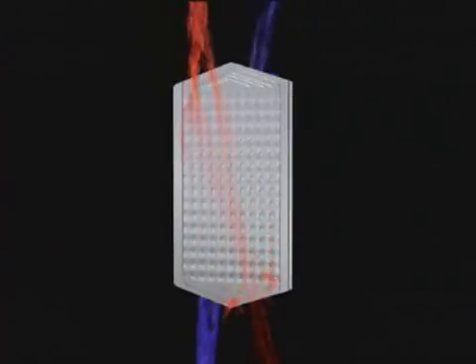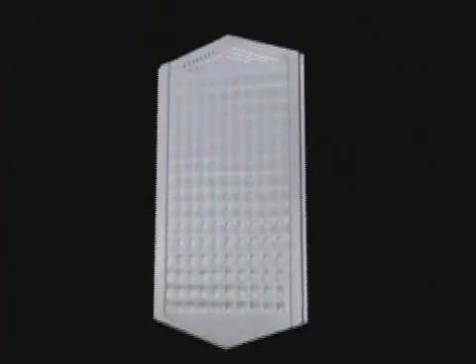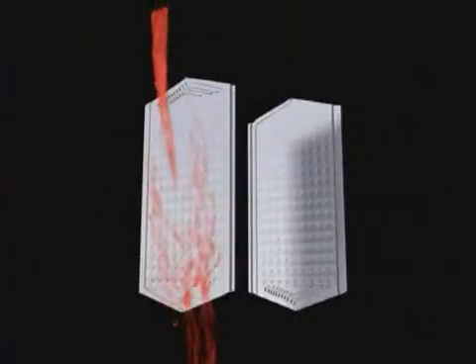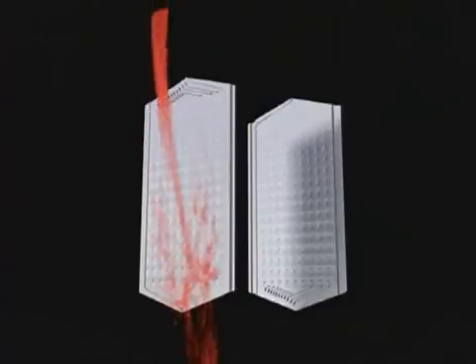This arrangement is the most efficient form of heat transfer and eliminates the typical diagonal temperature profiles found in cross-flow exchangers. The undulations on the plate surfaces provide turbulence and increase the thermal efficiency of the surfaces. Because it is impractical to duct alternating hot and cold gas streams to each plate, the entry and exit of the stream is accomplished using 50% of the plate.